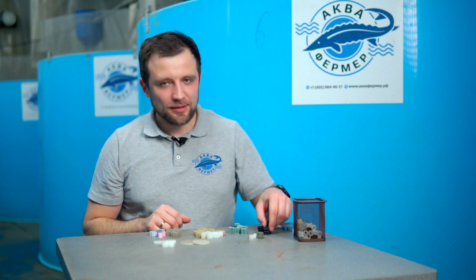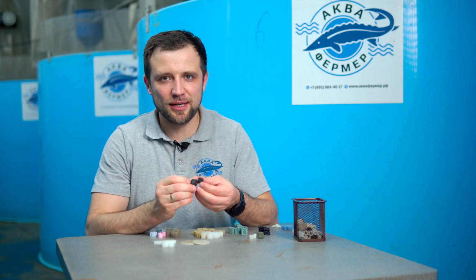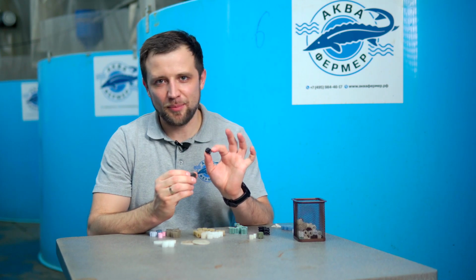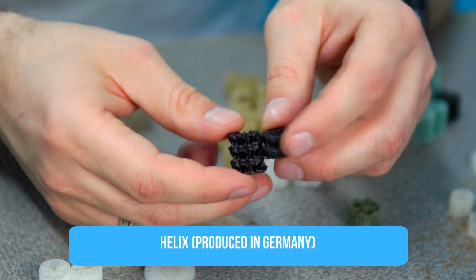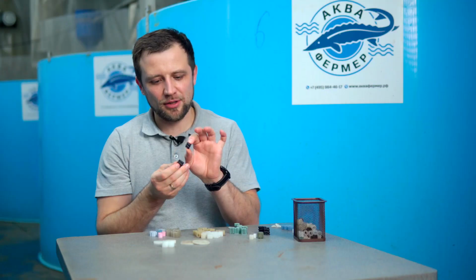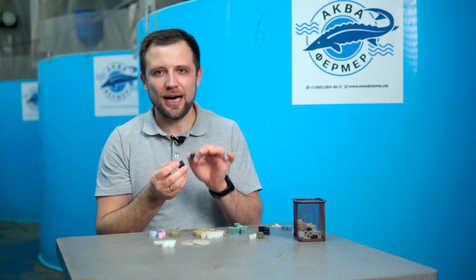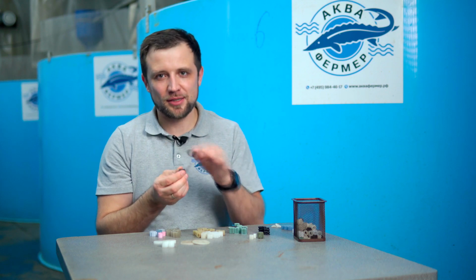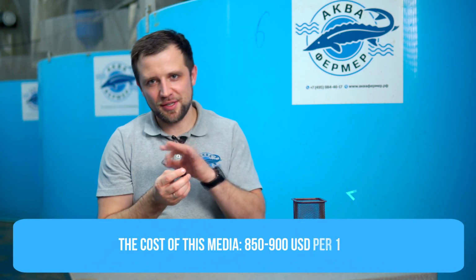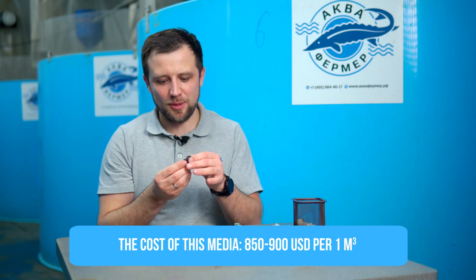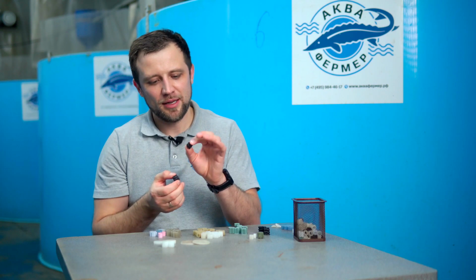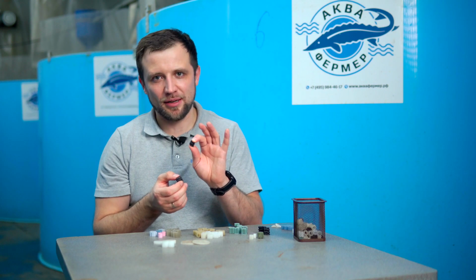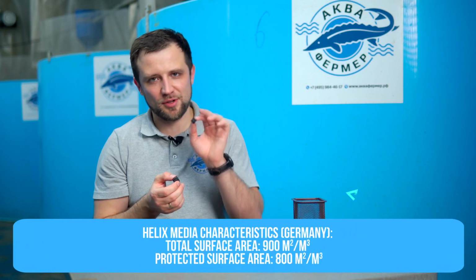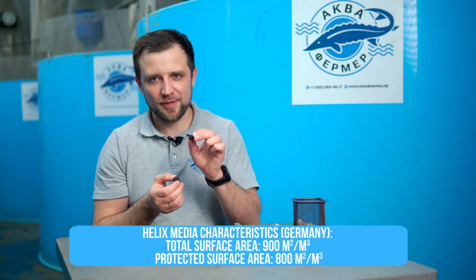This is one of my favorite types of media, from Helix. This is a German company. They produce really awesome media. At least, we have never had any complaints about their product. It's not cheap. It costs about $850–900 per cubic meter, but it has the highest characteristics in comparison with other commonly used types of media. That is 900 square meters total and 800 of protected area.